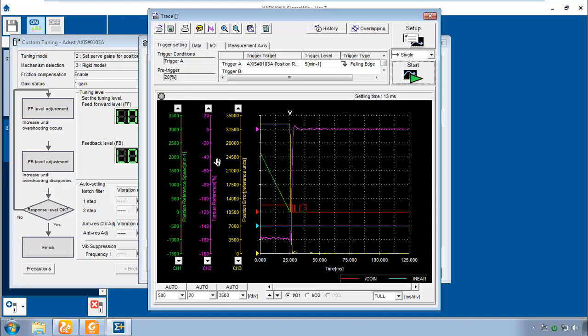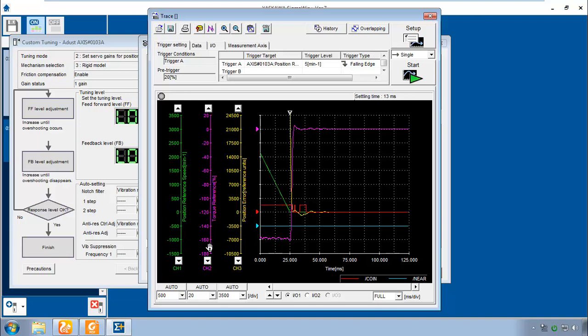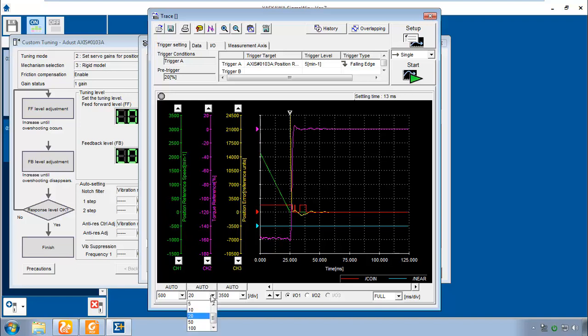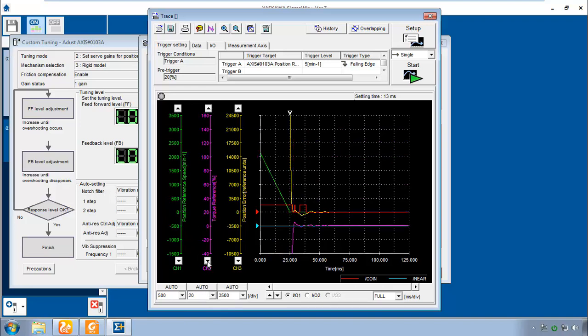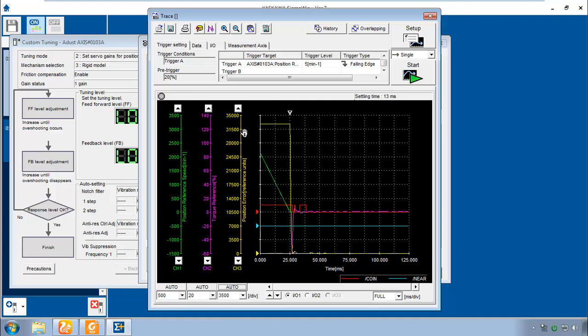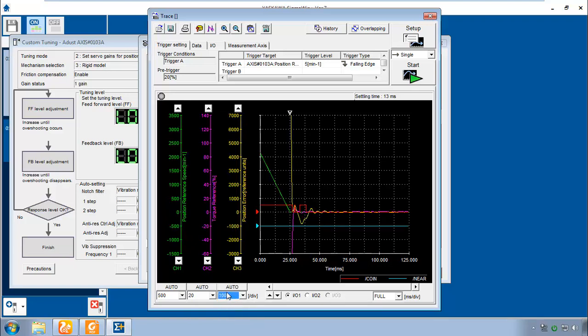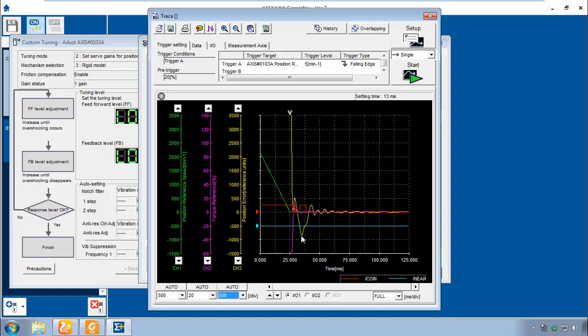And we have the same signals as before. But what I like to do is take that position error and you can shift it up. And now they're all lined up with basically the same zero. You can shift Torque down also. There's these auto scale, sometimes help. If you don't like the scaling, you can change it. I'm not really interested in the Torque, I'll shift the Torque down here. Now all the zeros are lined up. And now rather than zoom in, you can even play with these scales. Auto Scale automatically does the Offset and Scale, but you can choose a lower value here and you'll see. Now it becomes more apparent what's happening with the overshoot at the very end of the move. When I go to 500 pulses per division, you see how there is an overshoot. And that's why the coin signal kind of turns off and then turns back on again. Because all this time the motor went outside of that 466 pulse range for position complete.